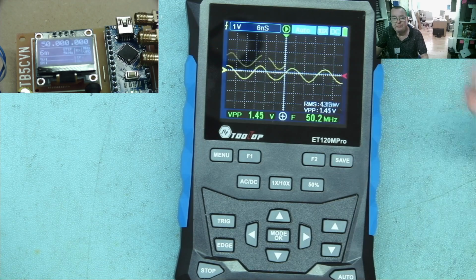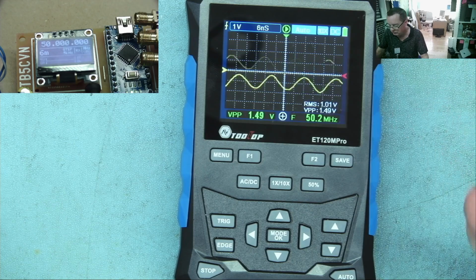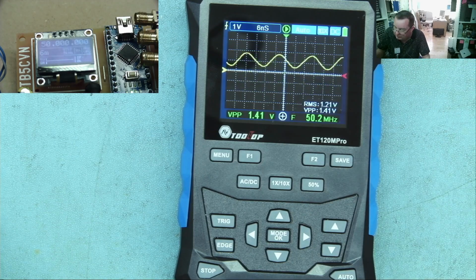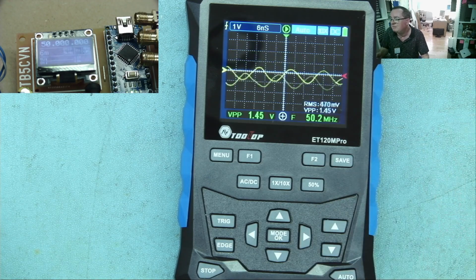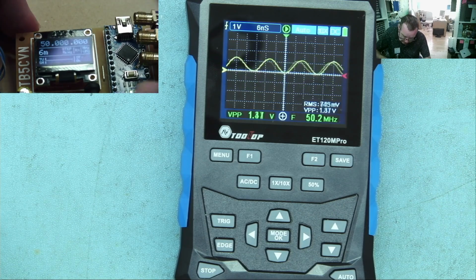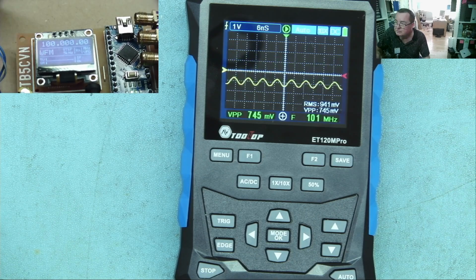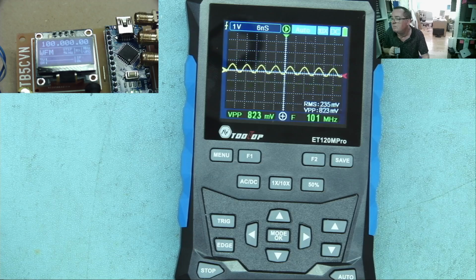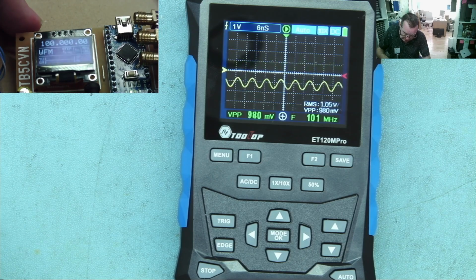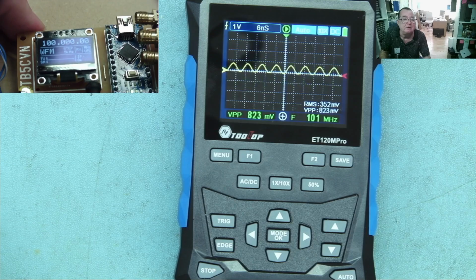Again, it takes a few attempts to lock it with this amount of noise in the signal. But it does effectively measure it. It tells me it is there. Go up again. So this is now at 100 megahertz. The rated maximum for this is 120.